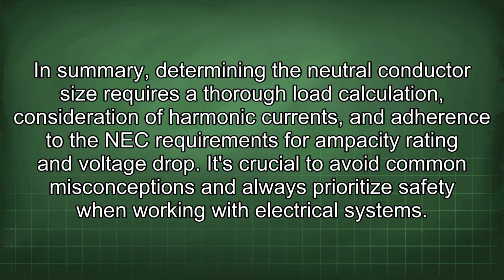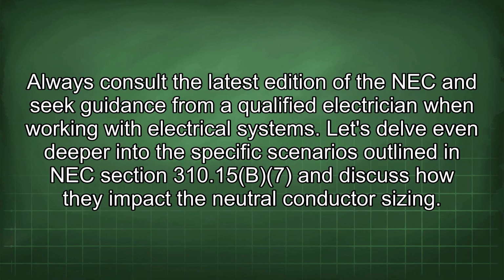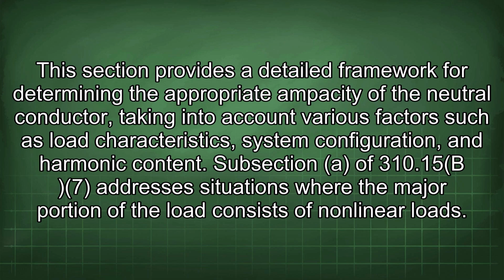It's crucial to avoid common misconceptions and always prioritize safety when working with electrical systems. Always consult the latest edition of the NEC and seek guidance from a qualified electrician when working with electrical systems. Let's delve even deeper into the specific scenarios outlined in NEC section 310.15(B)(7) and discuss how they impact the neutral conductor sizing. This section provides a detailed framework for determining the appropriate ampacity of the neutral conductor, taking into account various factors such as load characteristics, system configuration, and harmonic content.